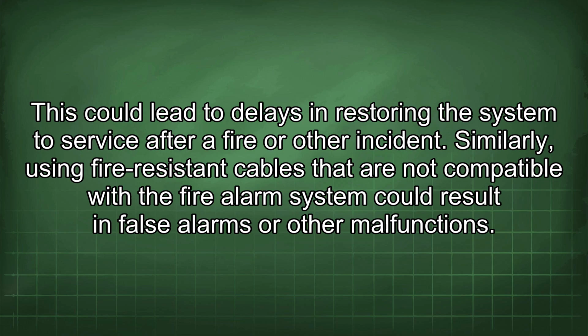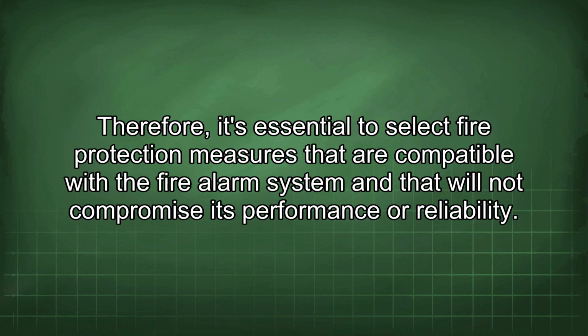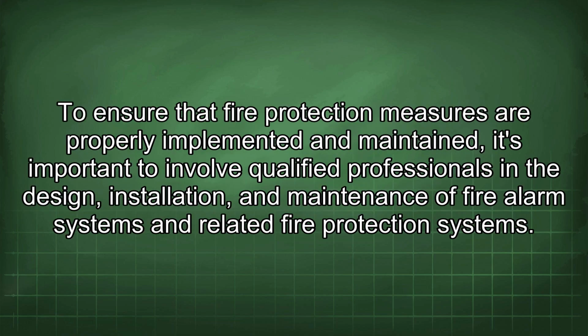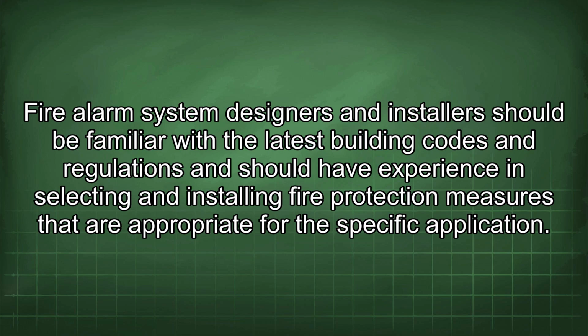Similarly, using fire-resistant cables that are not compatible with the fire alarm system could result in false alarms or other malfunctions. Therefore, it's essential to select fire protection measures that are compatible with the fire alarm system and that will not compromise its performance or reliability. To ensure that fire protection measures are properly implemented and maintained, it's important to involve qualified professionals in the design, installation, and maintenance of fire alarm systems and related fire protection systems. Fire alarm system designers and installers should be familiar with the latest building codes and regulations and should have experience in selecting and installing fire protection measures that are appropriate for the specific application.